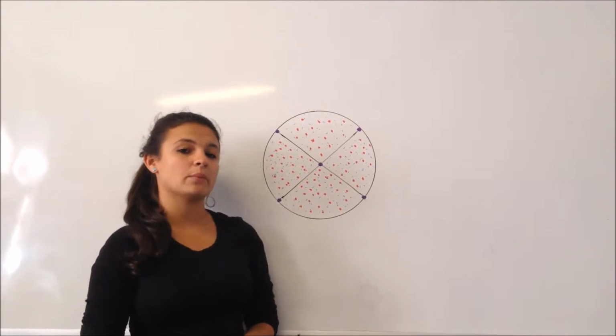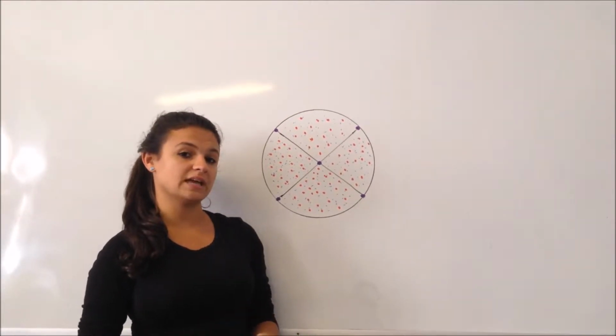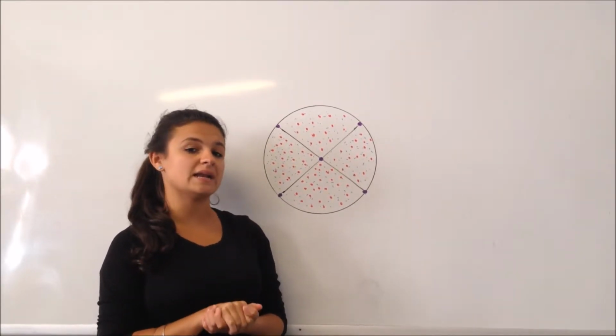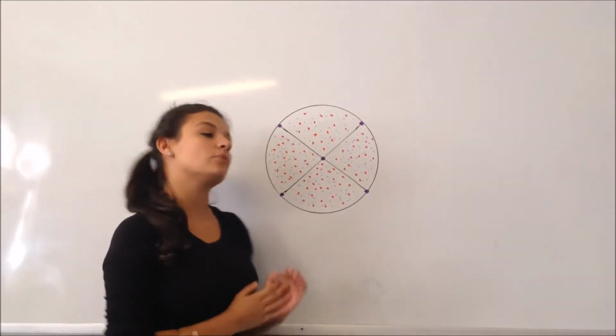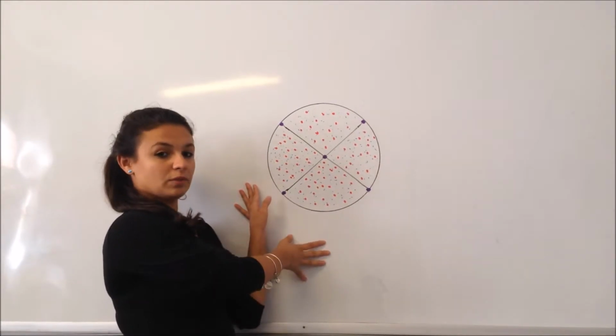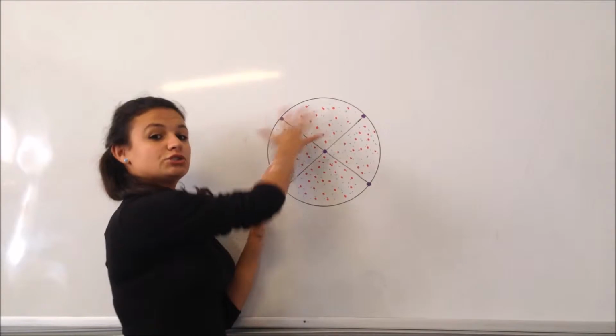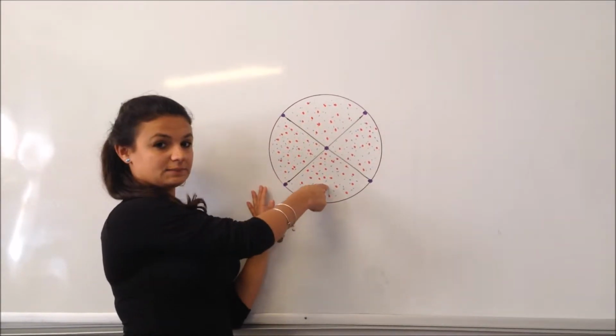Knowing a little bit more about what the internal structure of the tube looks like helps us understand what happens if the tube gets contaminated and how to fix it. On the board here, we have what the inside of the tube looks like. As you can see, there's two wires in the shape of an X, and surrounding those wires is measurable gas.